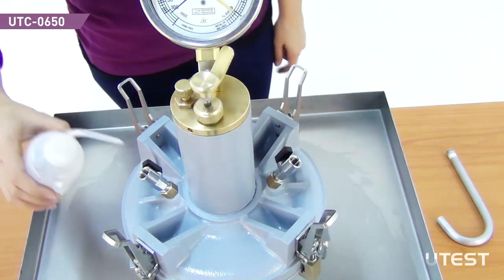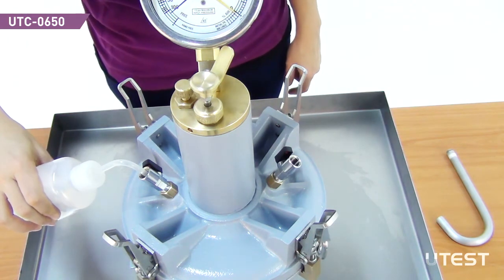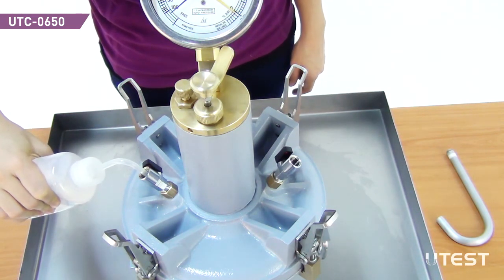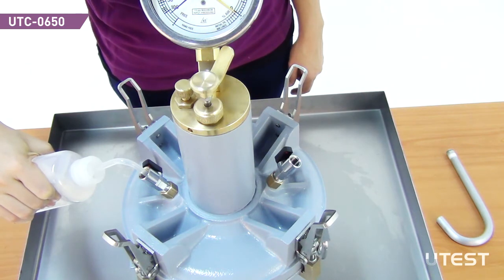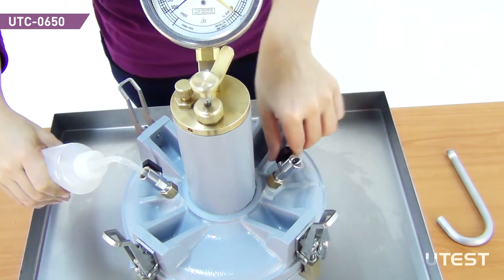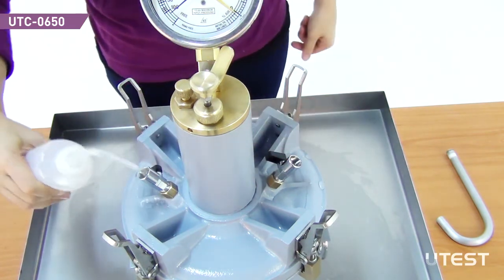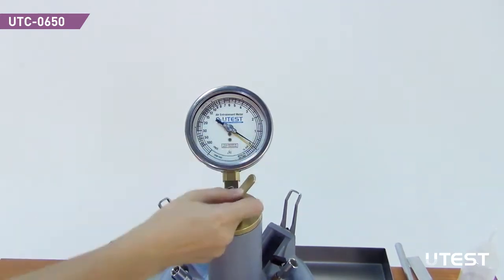Inject water through the petcock having the extension until all air is expelled and water bleeds from the second petcock and close them. Pump air into the air chamber until the gauge hand is stabilized at the initial pressure line.